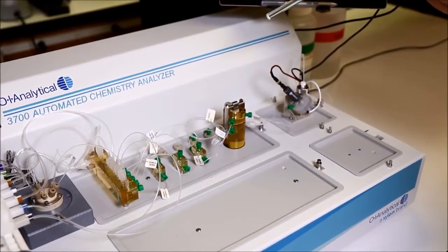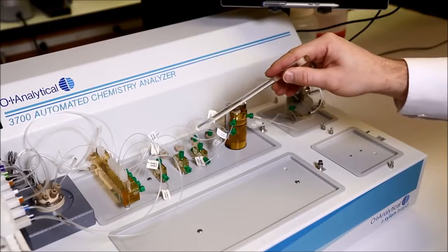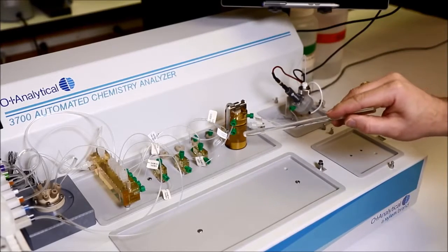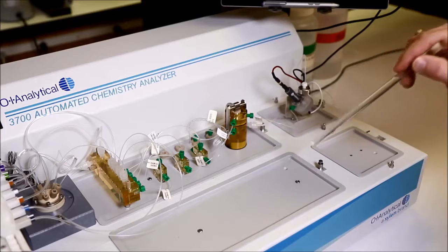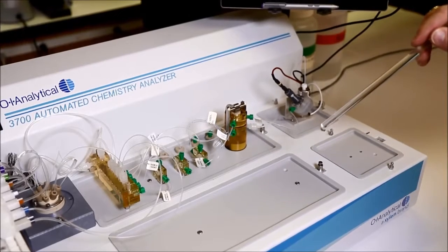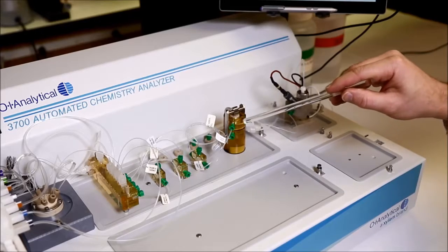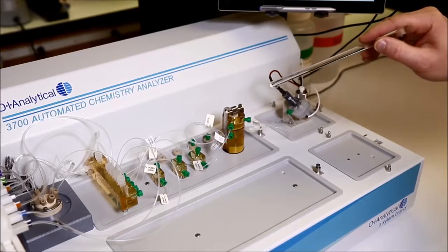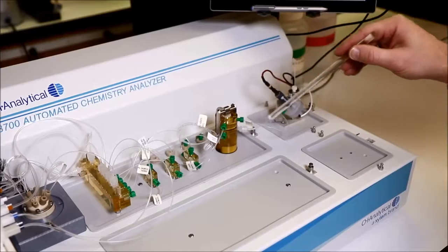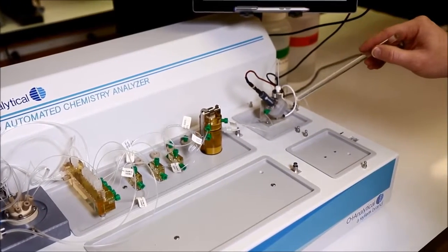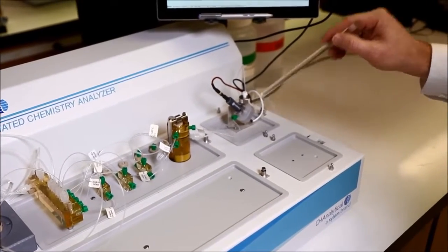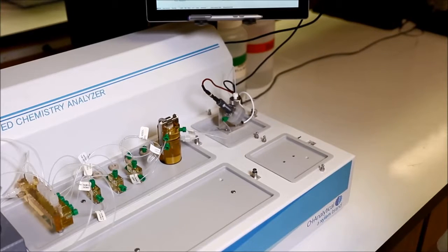After the metal cyanides have been disassociated, TA2 is added, the acidic sample stream passed on the lower side of a gas diffusion membrane, allowing cyanide to pass across into an alkaline receptor stream, which is then flowed over to the amperometric cell where the cyanide is measured directly.